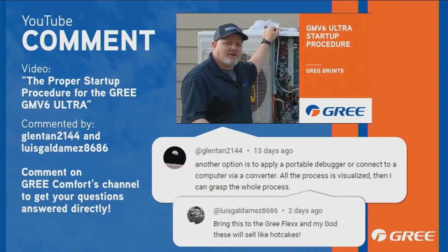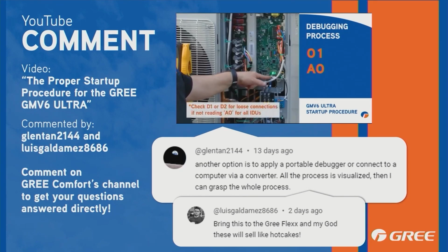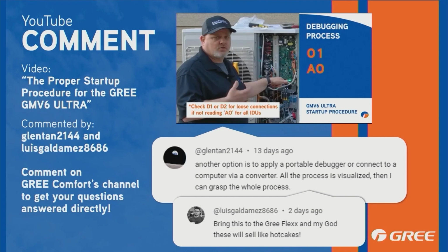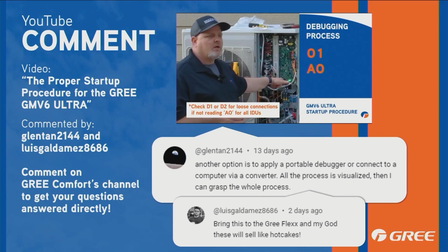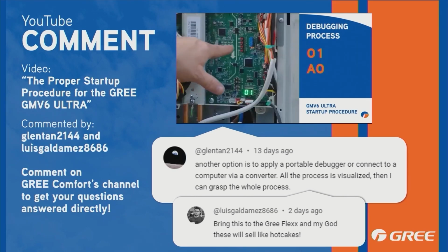Now, I will say that you can also see all that information through a wired controller if your system has one. You can see the pressures, temperatures, the target compressor speed, the target hertz, your DC bus. Instead of pulling out a meter and measuring the DC voltage on your inverter board, you can see what that's being measured at at the wired controller or at a portable debugger. Greg, would you like to add something to that?